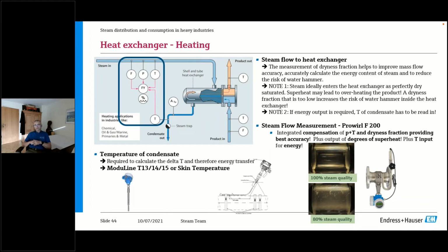And often you also find that the steam here is wet. So again, important: measure the dryness fraction, measure pressure and temperature to know where you are on the Mollier chart. And if you want to know the energy that you pass on to your process, I would read in an external temperature. You can use such a skin temperature measurement here. This is something we are providing, and you read that in using the 4-20 current input into the Vortex meter. You can also use digital input, then you know the energy. How much HFG are you passing on in reality to your heat exchanger? So again, Prowirl F200, best solution for such a case.